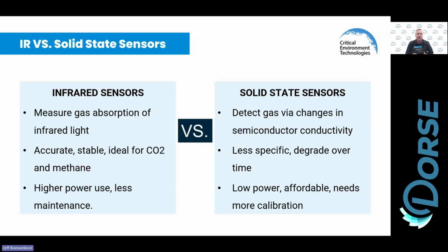This guy here, you could also add a third sensor. So it's got the two sensors built in. You could add a third sensor like hydrogen or methane or propane or a refrigerant and have a fully self-contained 3-gas system. Very cost effective when you're working on those smaller applications, right? Say you're working on a fire hall, very popular for fire halls. Maybe it's a police station. Maybe it's a small vehicle repair shop where you just need 1 or 2 sensing locations. This is a great option for that, right?